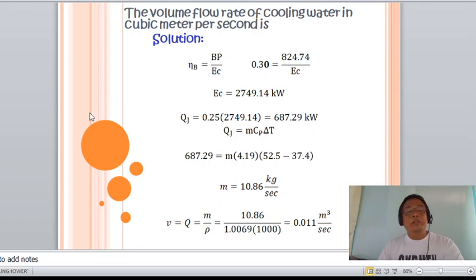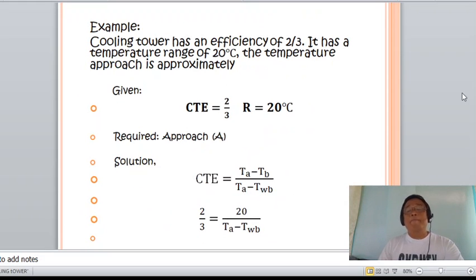Knowing also that the heat carried by the jacket water is equal to m Cp delta T, substituting now the values, Q_J of 687.29 is equal to mass multiplied by 4.19, which is the specific heat of water at constant pressure, multiplied by the change in temperature between the entering and leaving water. So, the mass now is equal to 10.86 kilograms per second. Changing this to cubic meter per second, that is equivalent to 0.011 cubic meter per second. So, problems in cooling tower are sometimes easy and sometimes become complicated. This previous example is an application of the performance of a diesel engine involving a cooling tower.